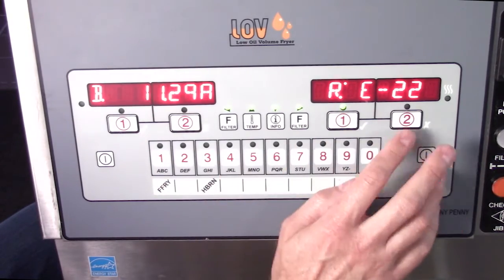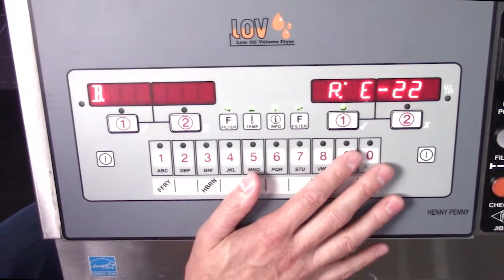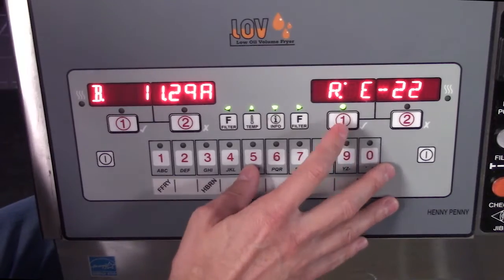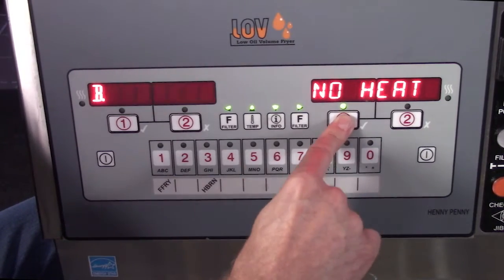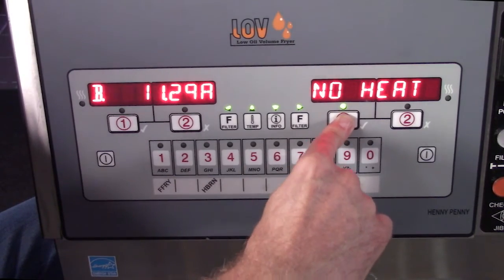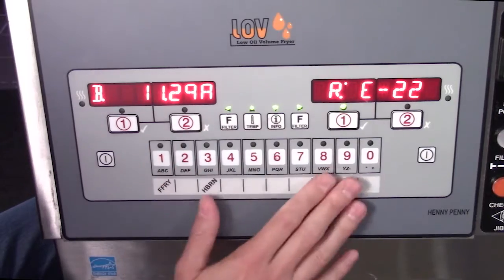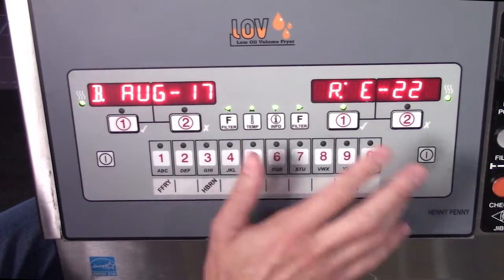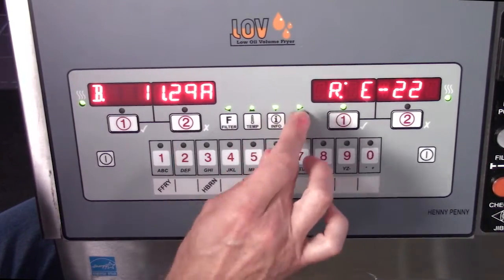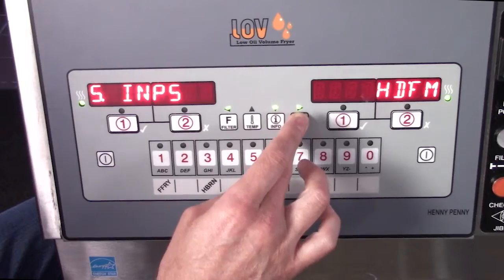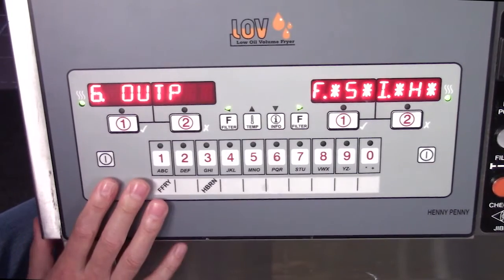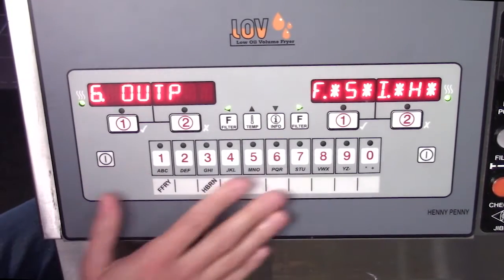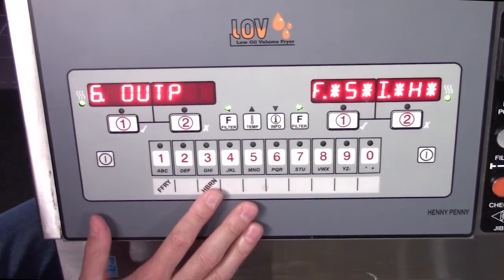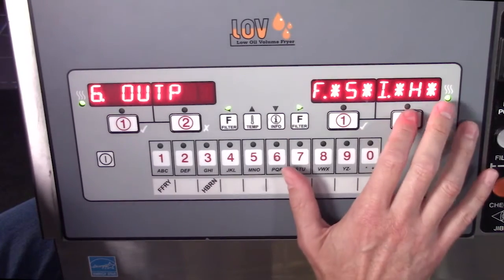Let's say you get out there, you don't remember what these error codes are, you can always press the number one check mark, and it tells me, oh, it's a no heat error code. So confirm the error code. That's best practices on that part of it. So let's go ahead and scroll on over, and I want to go to my outputs test. So this has to do with any of my outputs for my heat system, and we'll go through this quickly here to explain it.